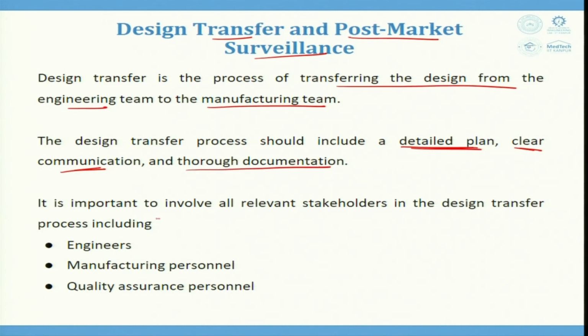It is important to involve all relevant stakeholders in the design transfer process, which include the engineers who have designed and given the design specifications for the prototype or the product finally that you would like to manufacture later, the manufacturing personnel who are going to actually manufacture because they know what setup is required or is available with them, then quality assurance personnel who would make sure that the regulatory requirements are well met.